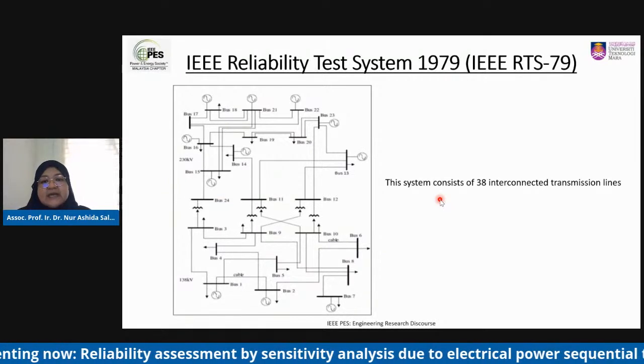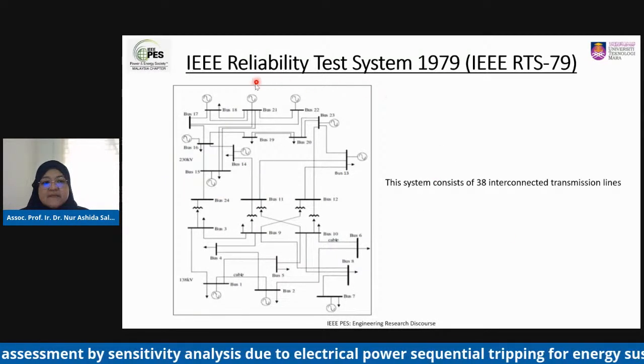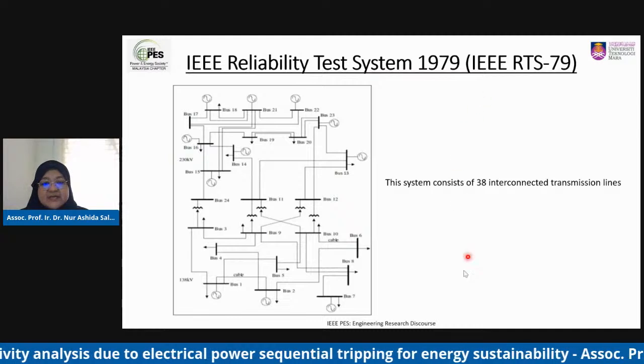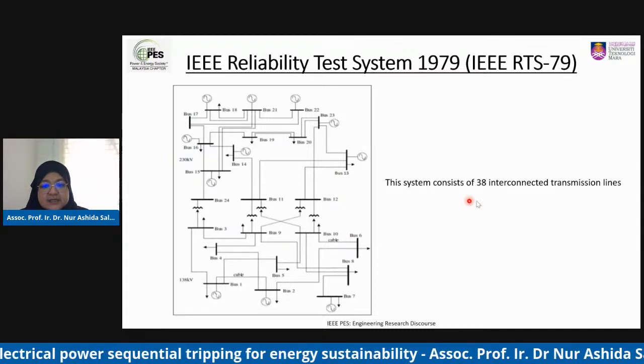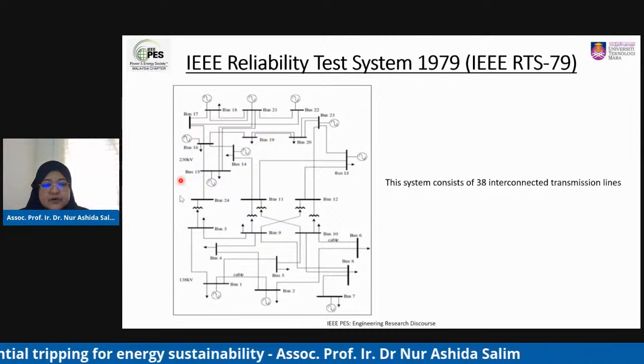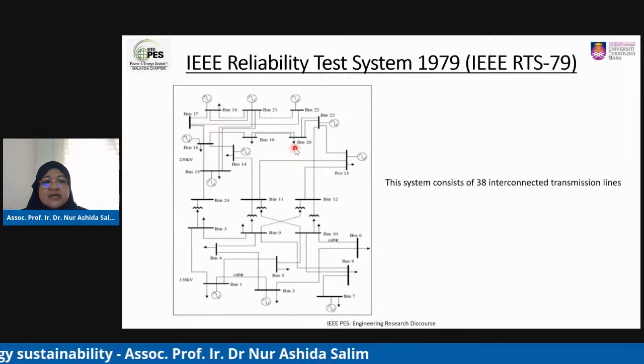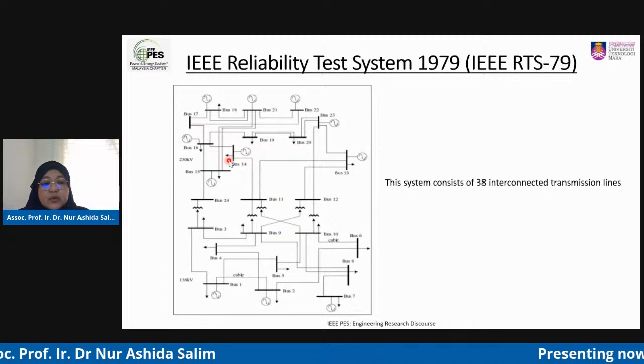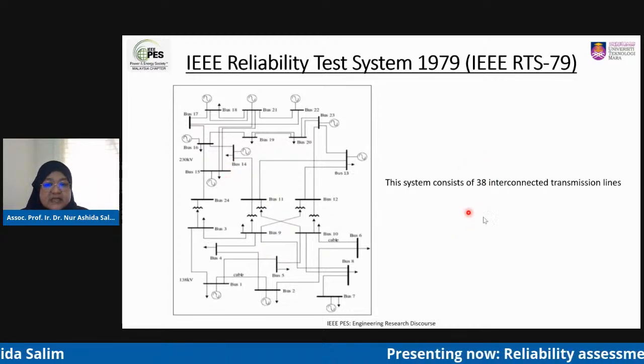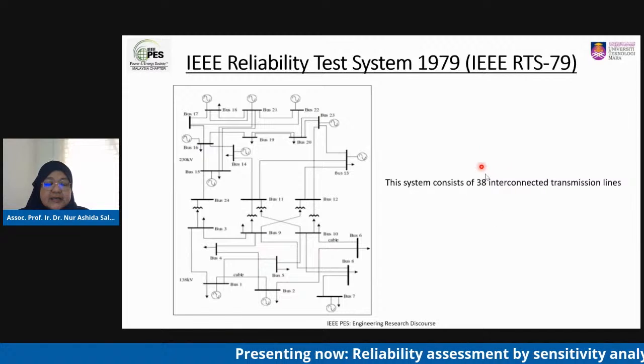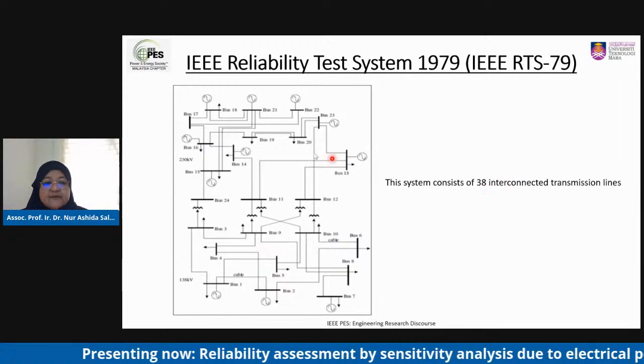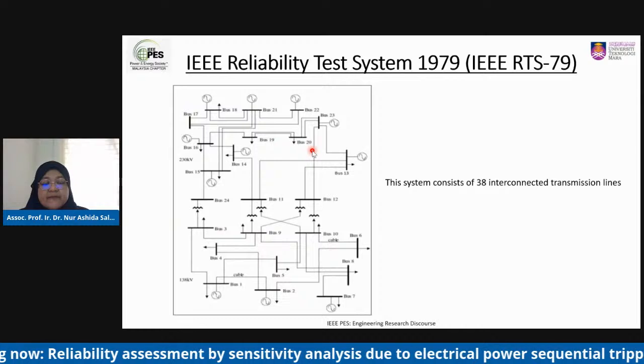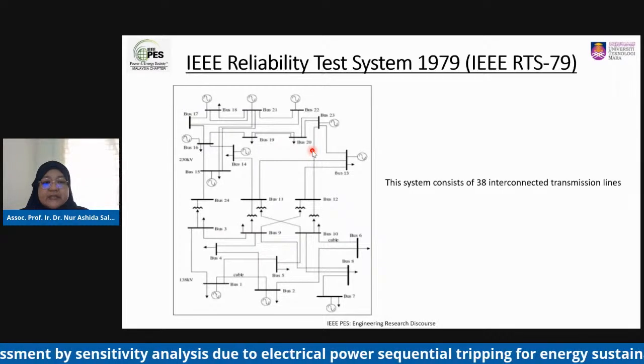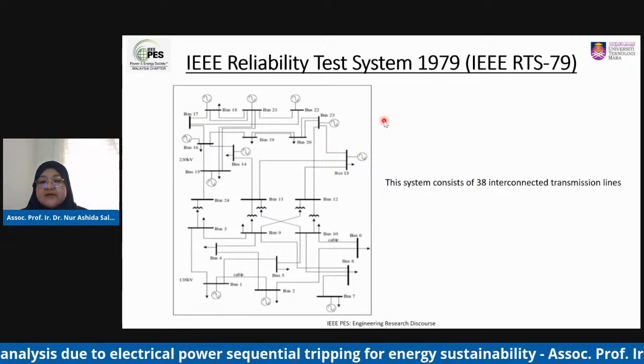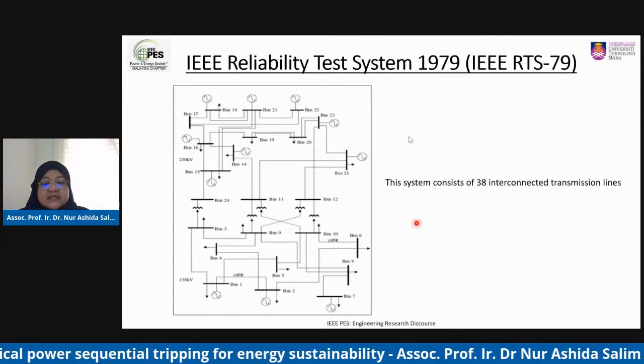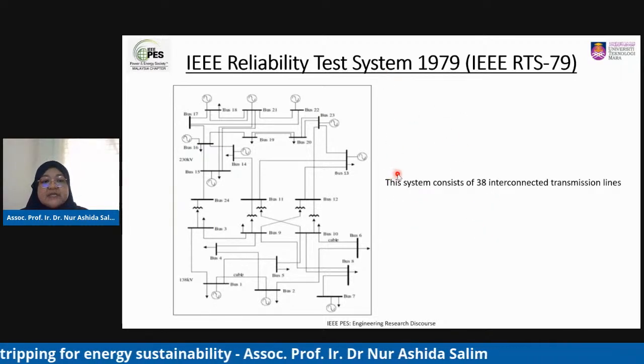The test system I'm using in this study is the IEEE Reliability Test System 1979, which consists of 38 transmission lines. For this study, I performed tripping one by one from line number 1 until line number 38, and tabulated the probability of the system to collapse due to that particular line tripping. So I have the results for all 38 transmission lines as the initial tripping.